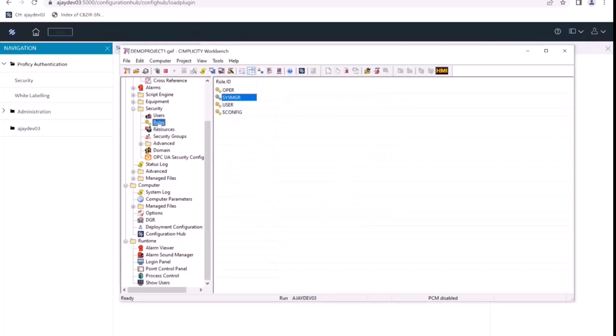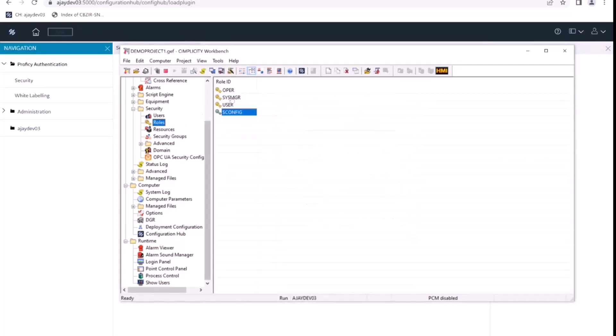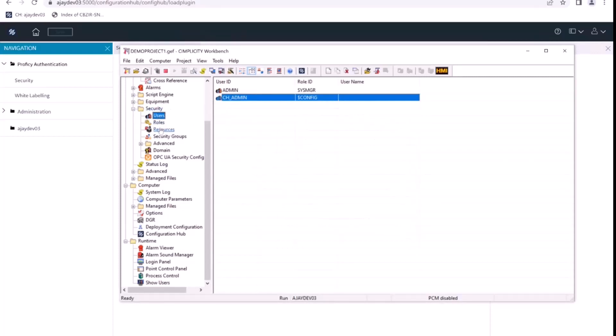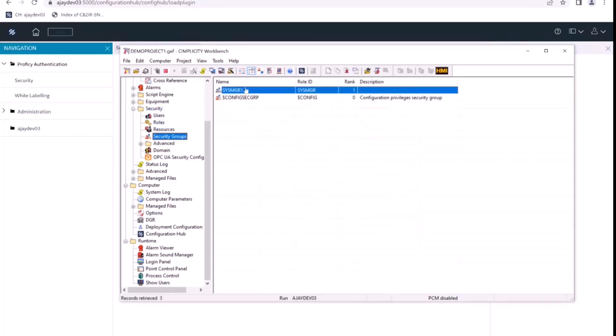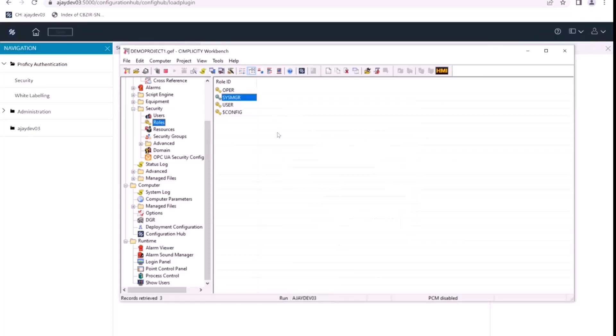Why did that happen? If you look at the roles, config has process control, but sysmanager doesn't. Looking at the users in security groups, sysmgr1 is the higher-ranked security group. So ch_admin logged into CIMPLICITY is assigned sysmgr1, which gives the sysmgr role. Since the sysmgr role doesn't have process control, we get the error that you do not have the process control privilege.